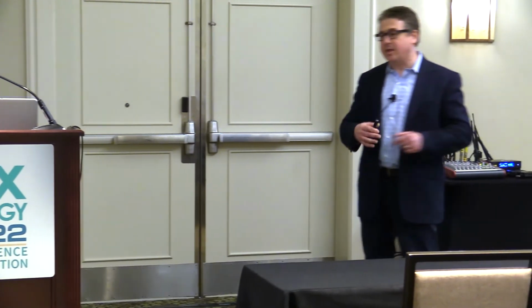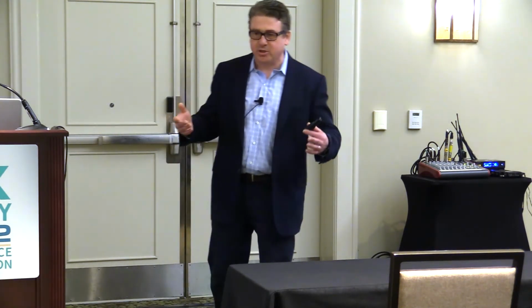...in a lab building you have a biological safety cabinet, and the cabinet is on emergency power, but not the fan that drives it. The reason is there was never a procedure that called for that cabinet to operate in emergency mode.